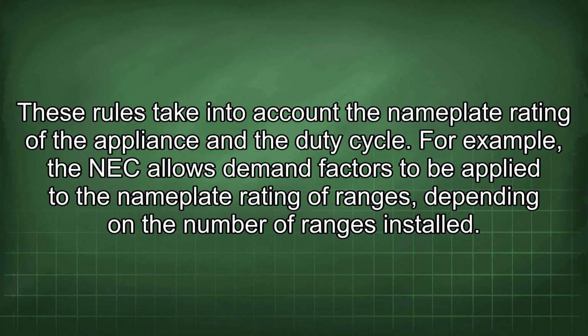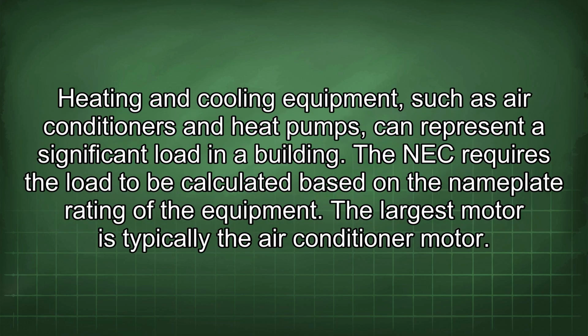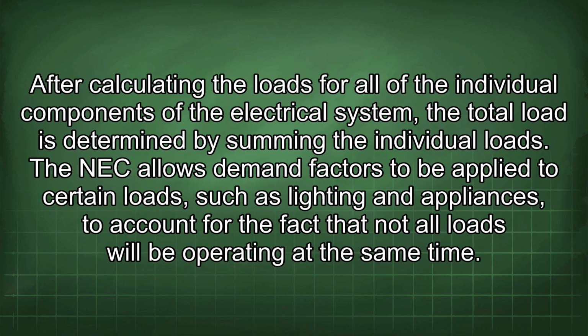of ranges installed. Heating and cooling equipment, such as air conditioners and heat pumps, can represent a significant load in a building. The NEC requires the load to be calculated based on the nameplate rating of the equipment. The largest motor is typically the air conditioner motor. After calculating the loads for all of the individual components of the electrical system, the total load is determined by summing the individual loads. The NEC allows demand factors to be applied to certain loads, such as lighting and appliances, to account for the fact that not all loads will be operating at the same time.